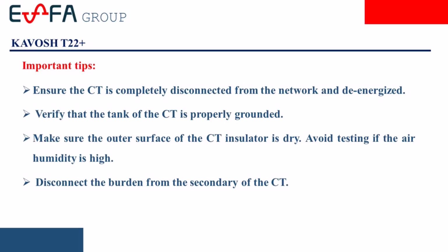Make sure the current transformer is completely disconnected from the network and de-energized. Verify that the tank of the CT is properly grounded. Ensure the outer surface of the CT insulator is dry and avoid testing in high humidity conditions. Disconnect the burden from the secondary side of the CT before testing.